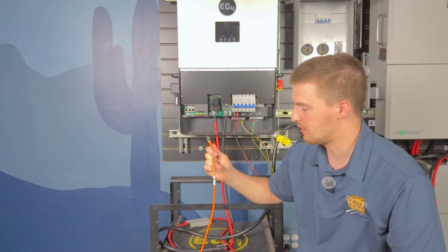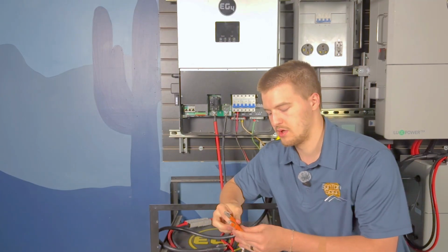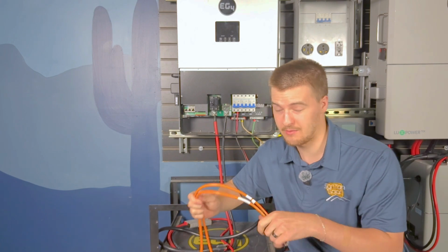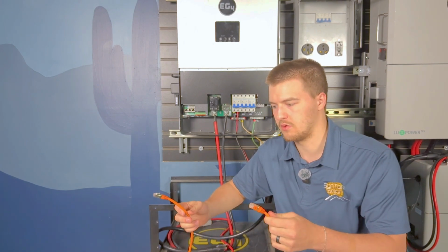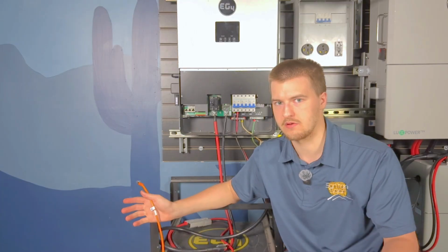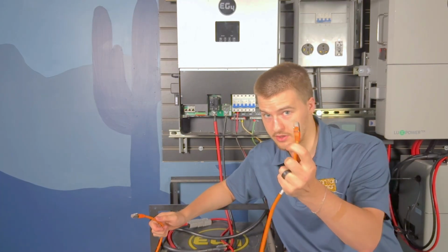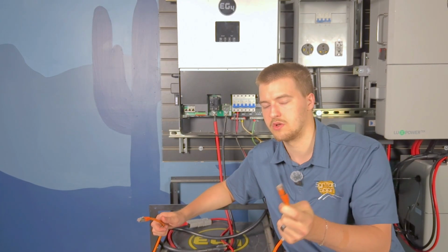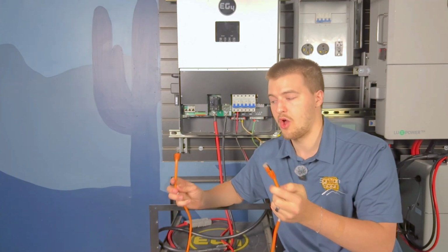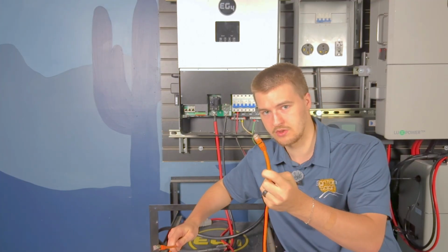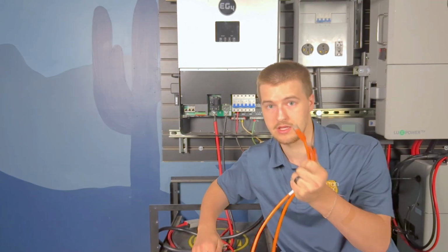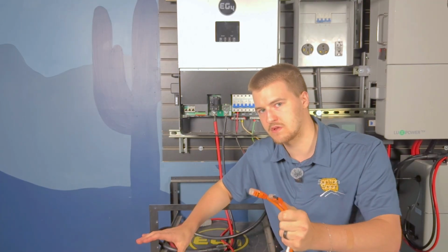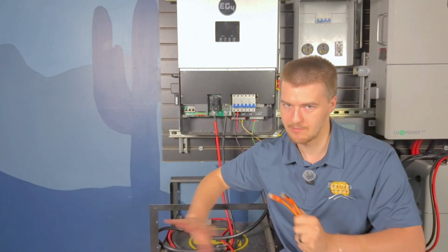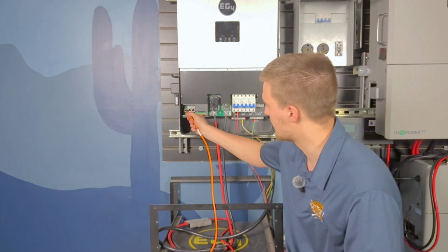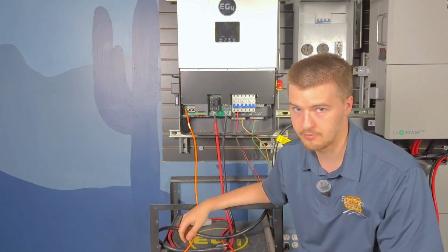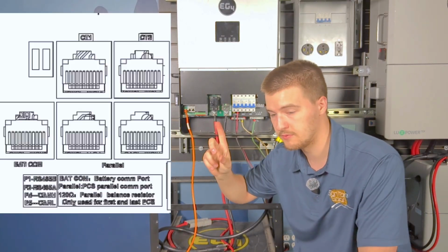You only need one of these. I've had multiple customers where, say they have 3 inverters and 6 batteries — they'll have 3 communication cables like this in their CAN ports, which is completely wrong. Only the master inverter needs the orange cable, and only the master battery needs the orange cable. Everything else is separate. So with my orange cable, I'm going to connect it to the battery COM port, which I'll show on screen now.